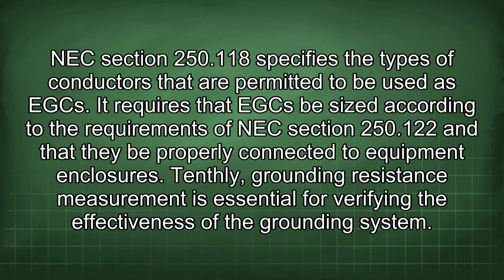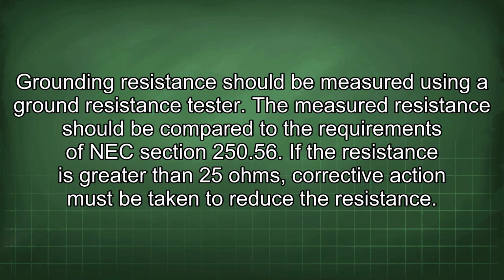It requires that EGC be sized according to the requirements of NEC Section 250.122 and that they be properly connected to equipment enclosures. Tenthly, grounding resistance measurement is essential for verifying the effectiveness of the grounding system. Grounding resistance should be measured using a ground resistance tester. The measured resistance should be compared to the requirements of NEC Section 250.56. If the resistance is greater than 25 ohms, corrective action must be taken to reduce the resistance.